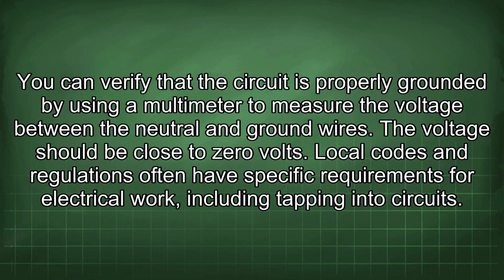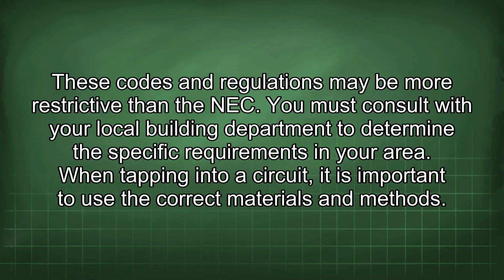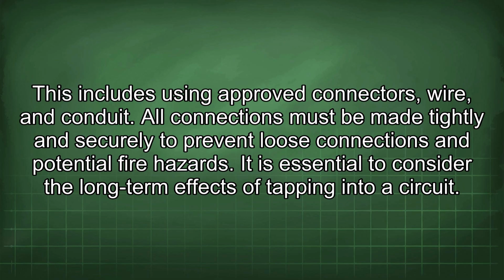including tapping into circuits. These codes and regulations may be more restrictive than the NEC. You must consult with your local building department to determine the specific requirements in your area. When tapping into a circuit, it is important to use the correct materials and methods. This includes using approved connectors, wire, and conduit. All connections must be made tightly and securely to prevent loose connections and potential fire hazards.